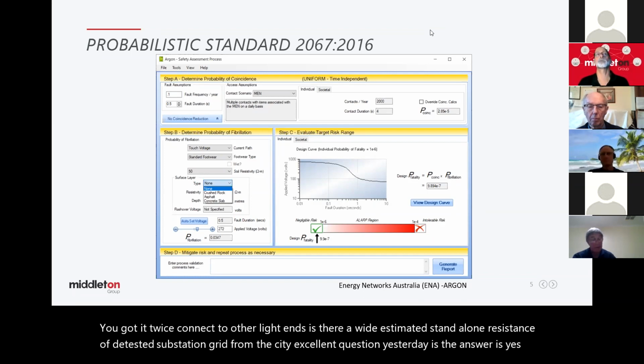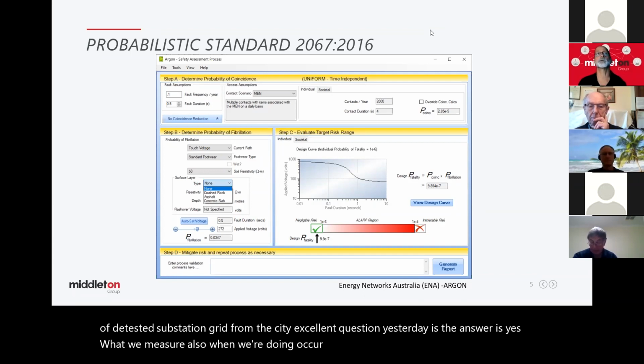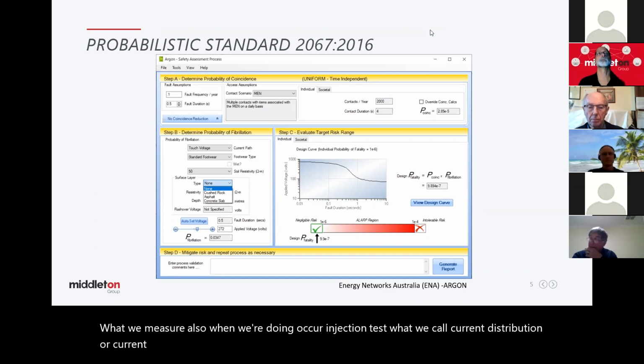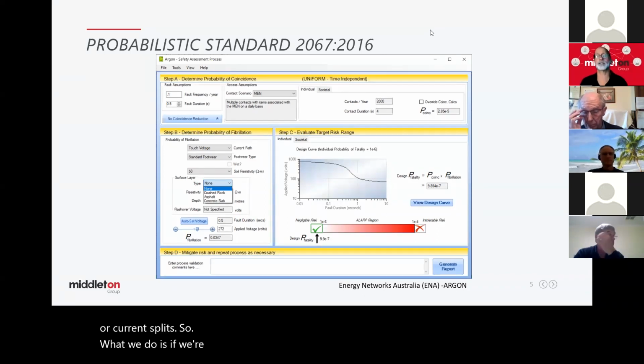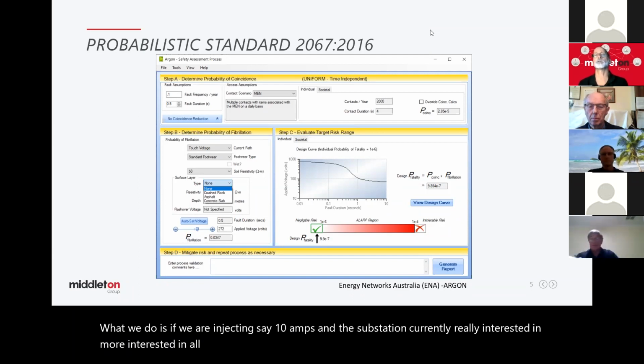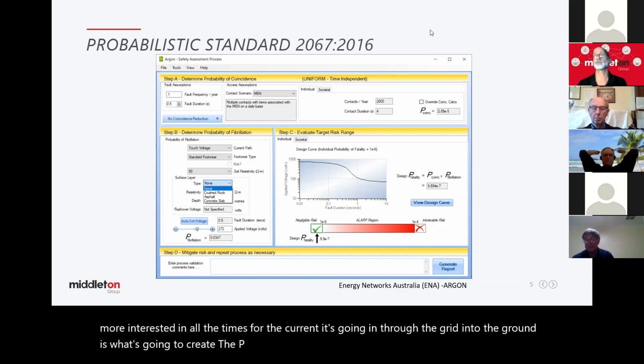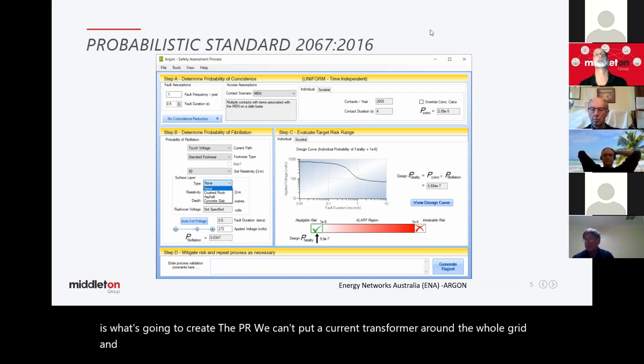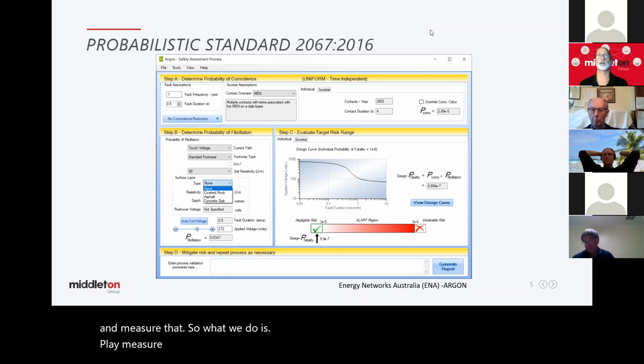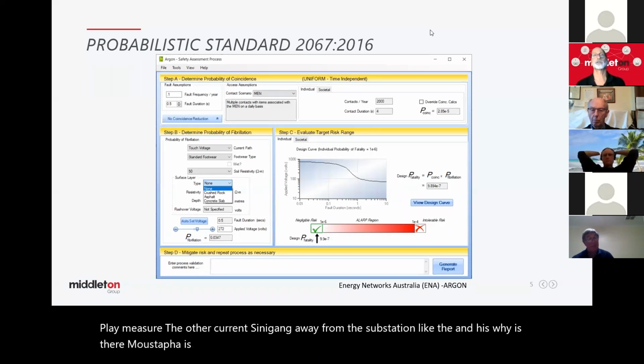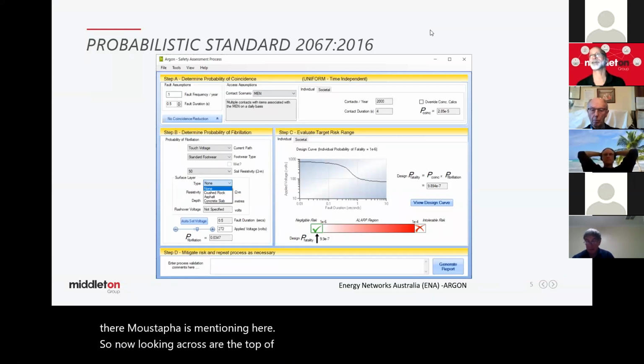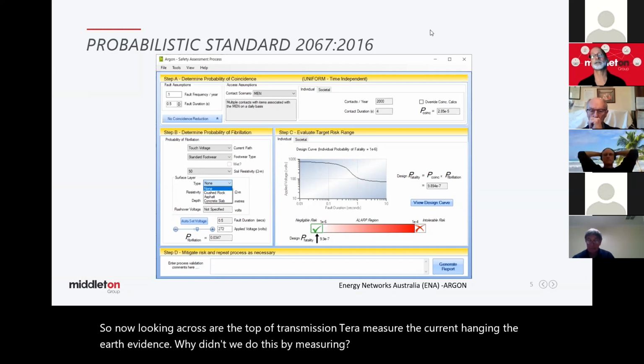What we also measure when we're doing a current injection test is what we call current distribution or current splits. So what we classically do is if we're injecting, say, 10 amps at a substation, the current we're really interested in is the current that's going in through the grid into the ground, as that is what's going to create the EPR. We can't put a current transformer around the whole grid and measure that. So what we do is we measure all the other currents that are going away from the substation, like the overhead earth wires that Mustafa is mentioning here.